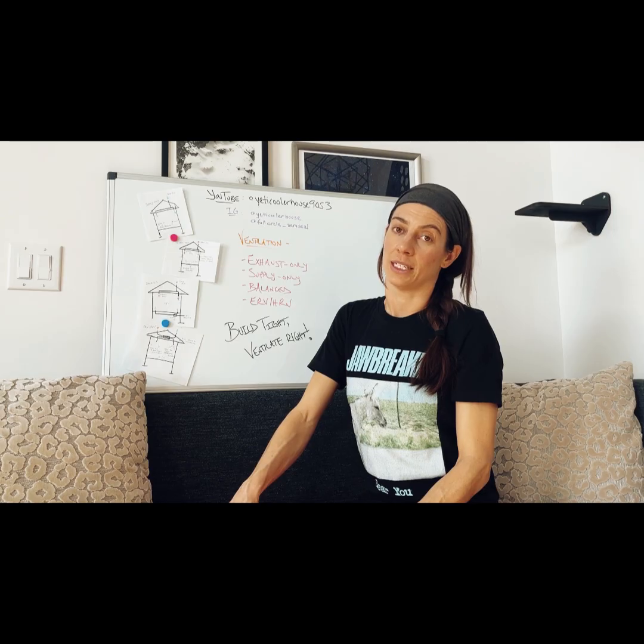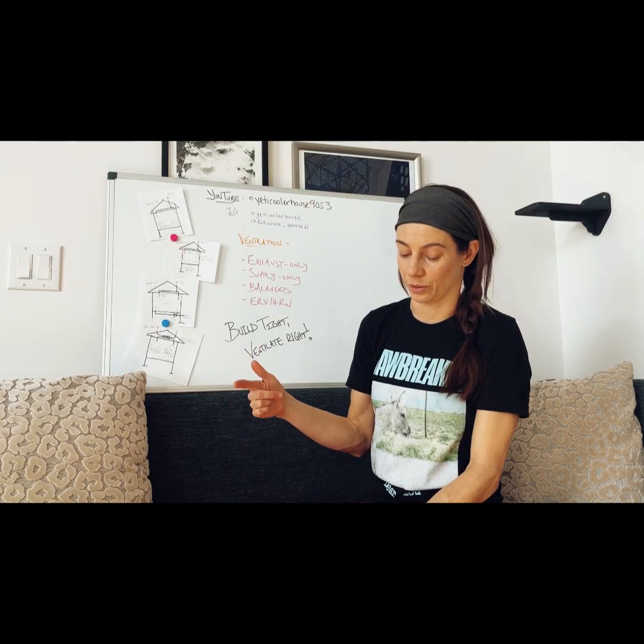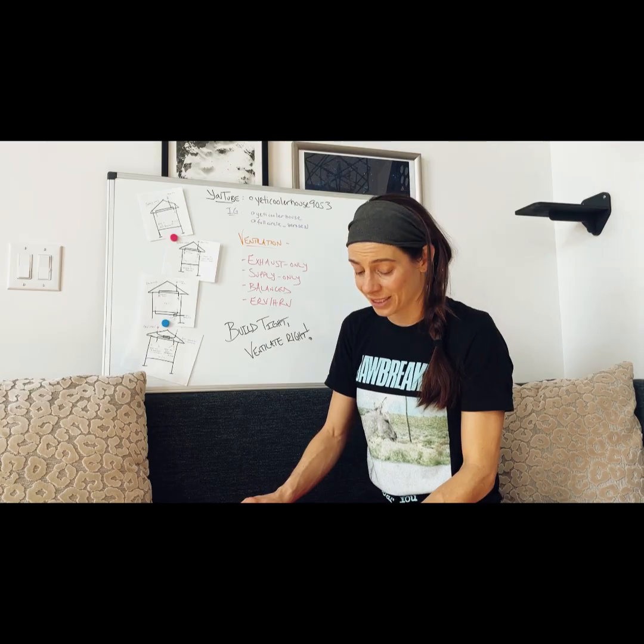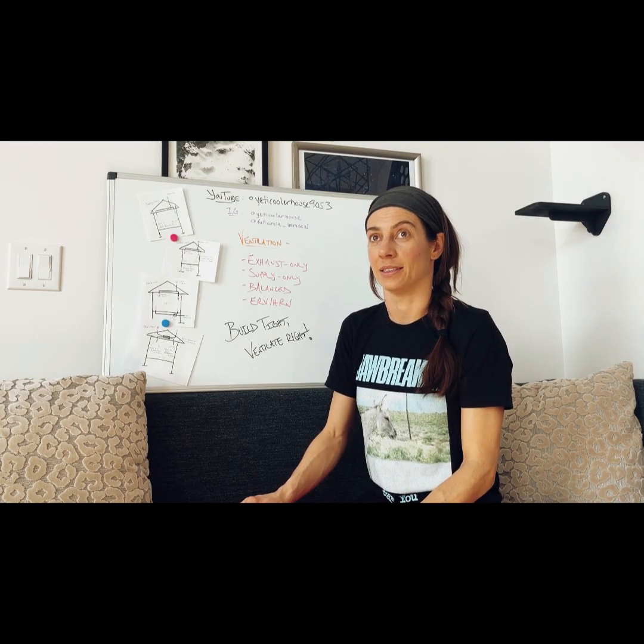Now, in warmer climates, a supply only system is more common. It's just a fresh air duct with a filter and a fan that pulls the fresh air from the outside and supplies it to the most occupied rooms, your bedrooms, living room. Backdrafting of the appliances would typically not be an issue because the house is pressurized. So that is an advantage.